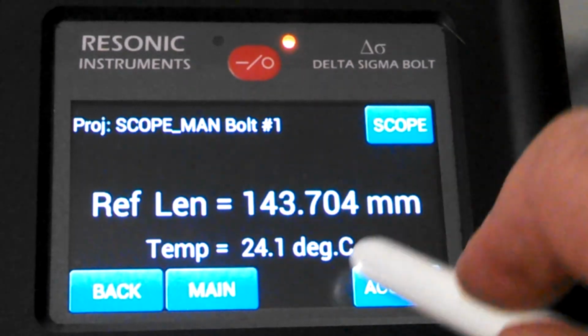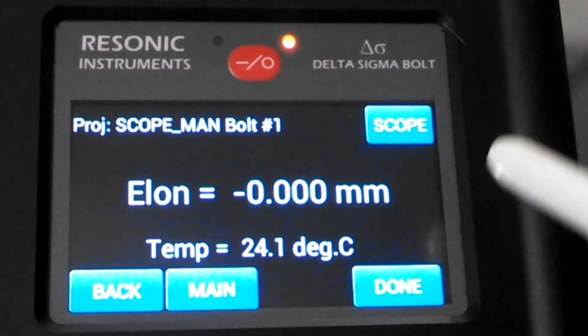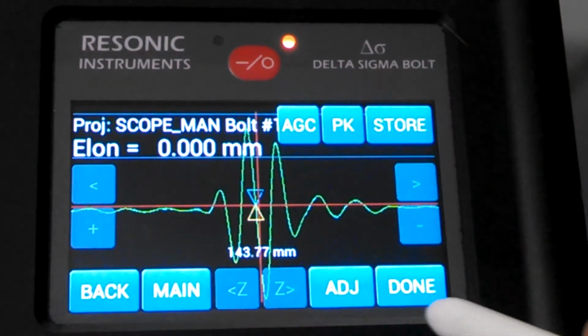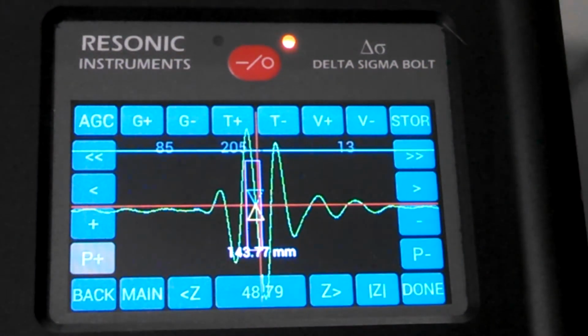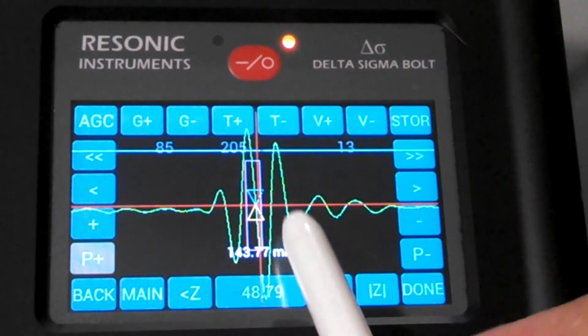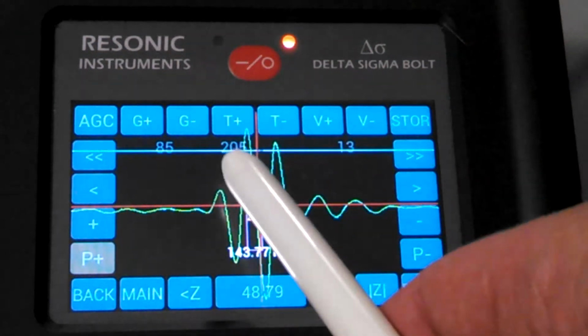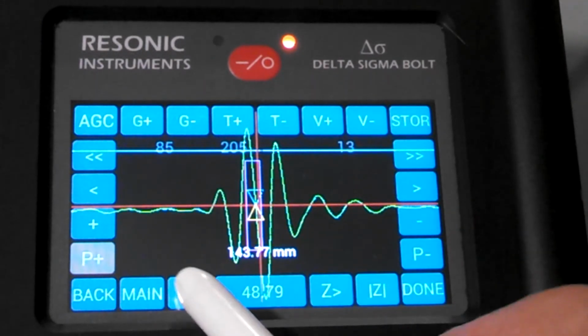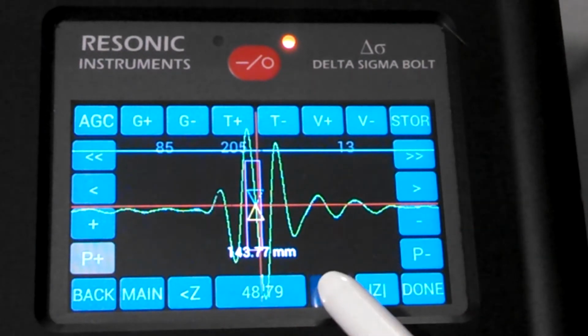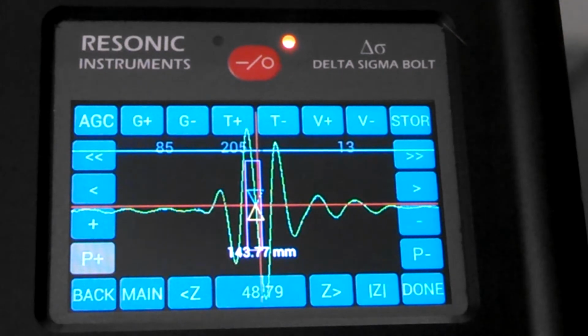So we'll accept that. We'll go back to elongation. We can go back to scope. We'll blow the signal up a little bit. And you can go into adjust here if need be. Remember, if you're tightening a bolt and it bends, it's going to distort the signal. You can come back in, and if the amplitude of this peak comes up because of bending, you can adjust the caret Z to bring the signal back to the zero crossing you were on.